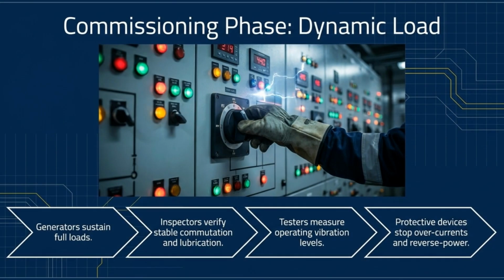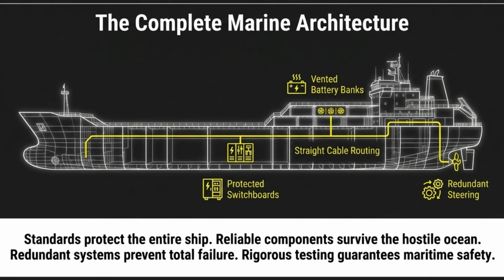Commissioning also includes dynamic load testing. Generators are run at full capacity, while inspectors verify vibration levels and the effectiveness of protective devices against overcurrents. In summary, these marine standards integrate every component of ship architecture. Through redundancy, testing, and rigorous design, they ensure maritime safety in the most demanding environments.